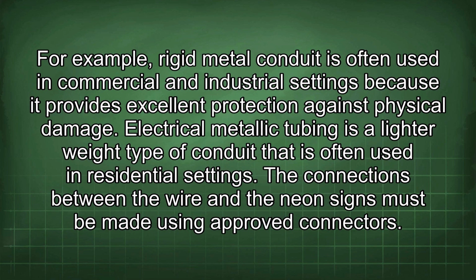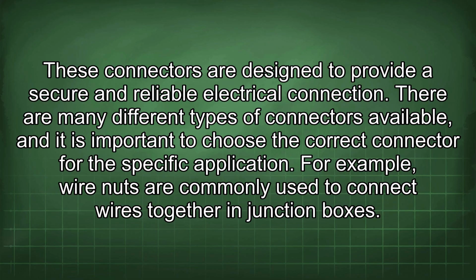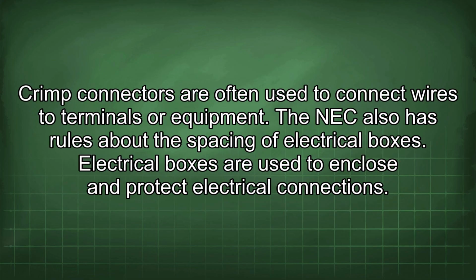The connections between the wire and the neon signs must be made using approved connectors. These connectors are designed to provide a secure and reliable electrical connection. There are many different types of connectors available, and it is important to choose the correct connector for the specific application. For example, wire nuts are commonly used to connect wires together in junction boxes. Crimp connectors are often used to connect wires to terminals or equipment.